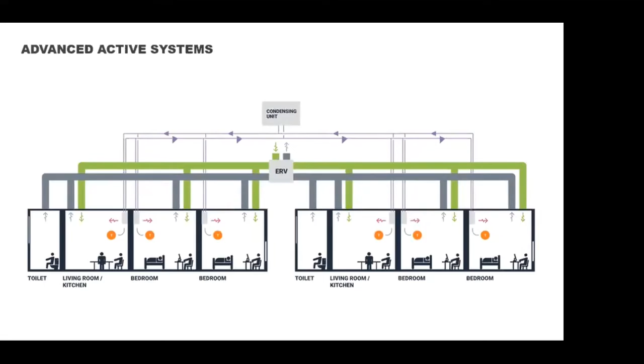The system results in a heating COP of 4.1 and a cooling COP of 4.2, which is quite good. The heating and cooling is decoupled from the ventilation, which is provided through a centralized dedicated outdoor air system, or DOAS, which has energy recovery built in. This unit provides a total heat recovery efficiency of approximately 84%, which is also quite high for a centralized unit.